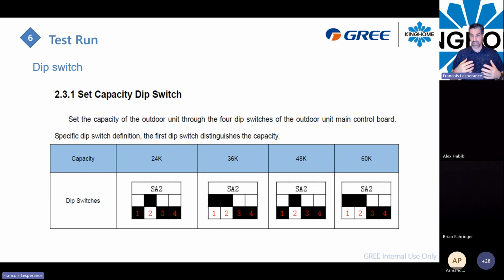One thing you can do is program the dip switch. You will do that because by default we're using two different cabinets, as I said. For a 3-ton unit, this is how the dip switch will be set as default. And for a 5-ton unit, this is how the dip switch will be set as default. It's the same picture, but one is for the 5-ton cabinet and one is for the 3-ton cabinet.